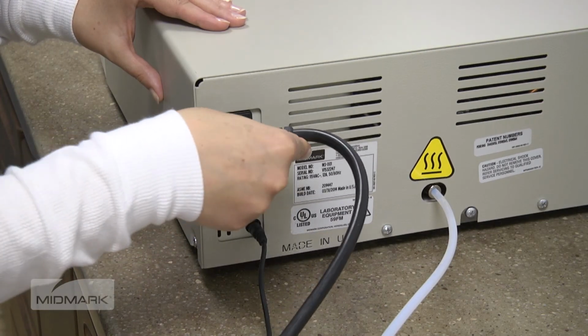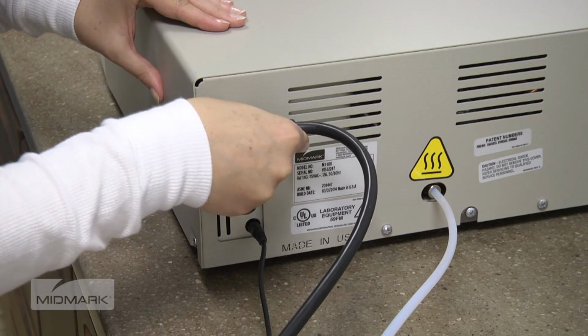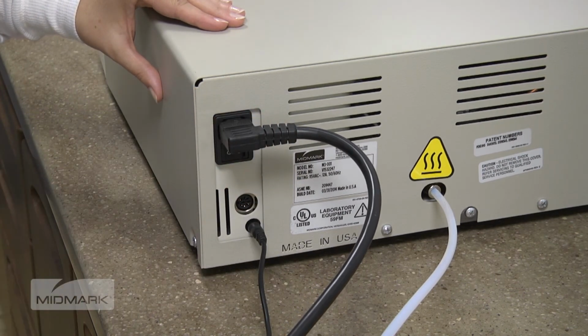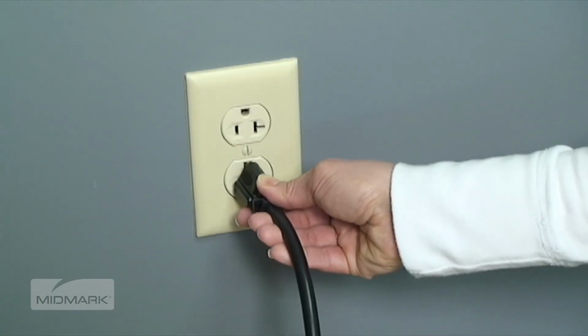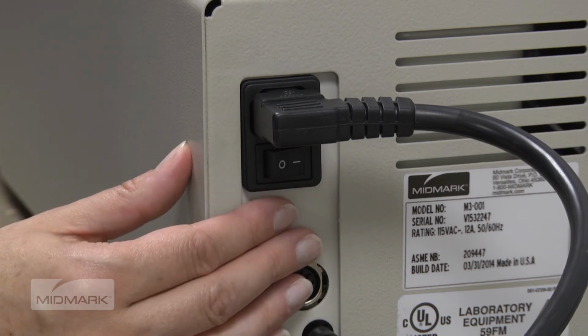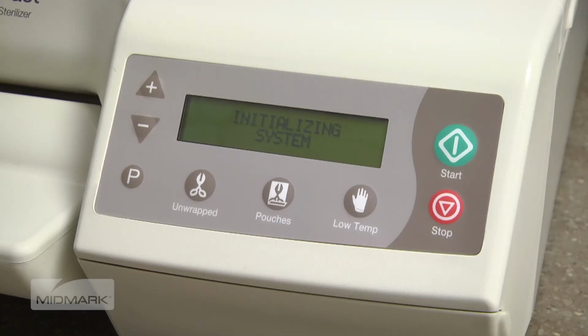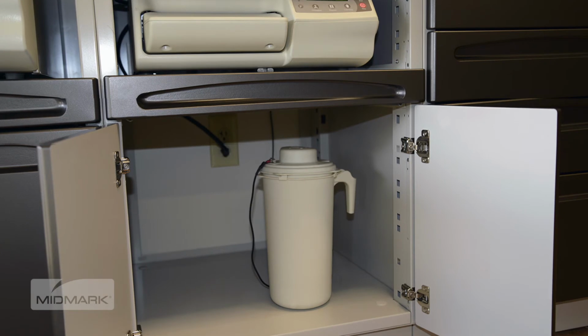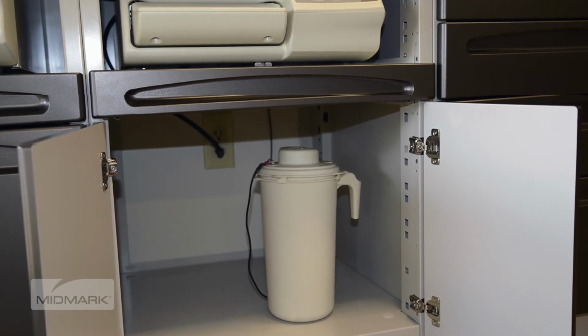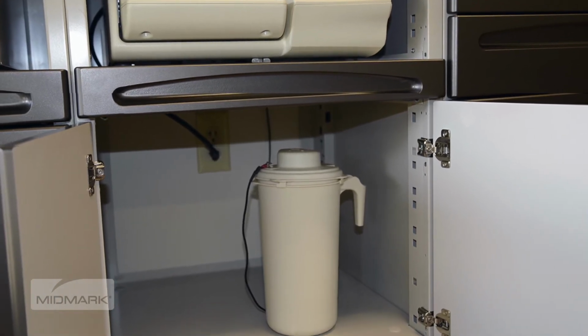After ensuring proper electrical requirements, attach the electrical cord to the back of the autoclave and then into the wall socket. Turn the unit power switch to on. This message will then appear on the display. Maintain a minimum of 6 inches of clearance above the condensing tank for proper steam ventilation.